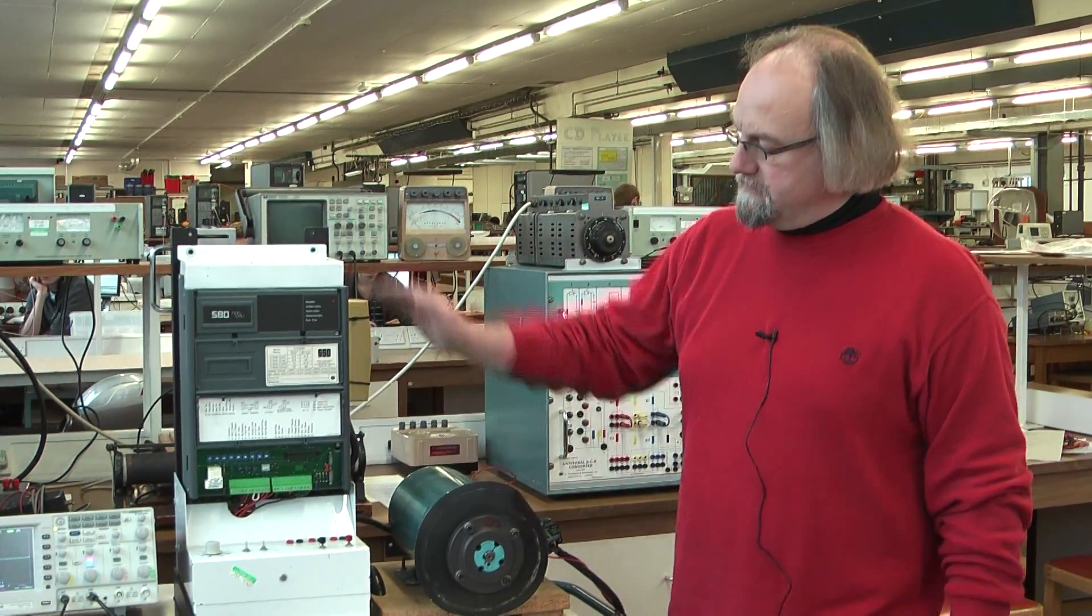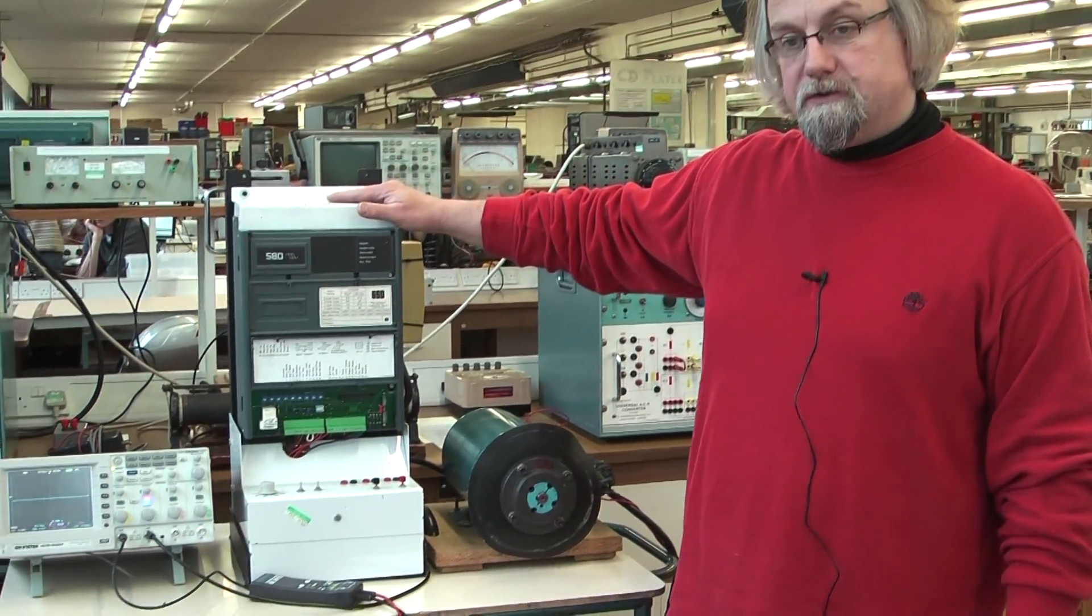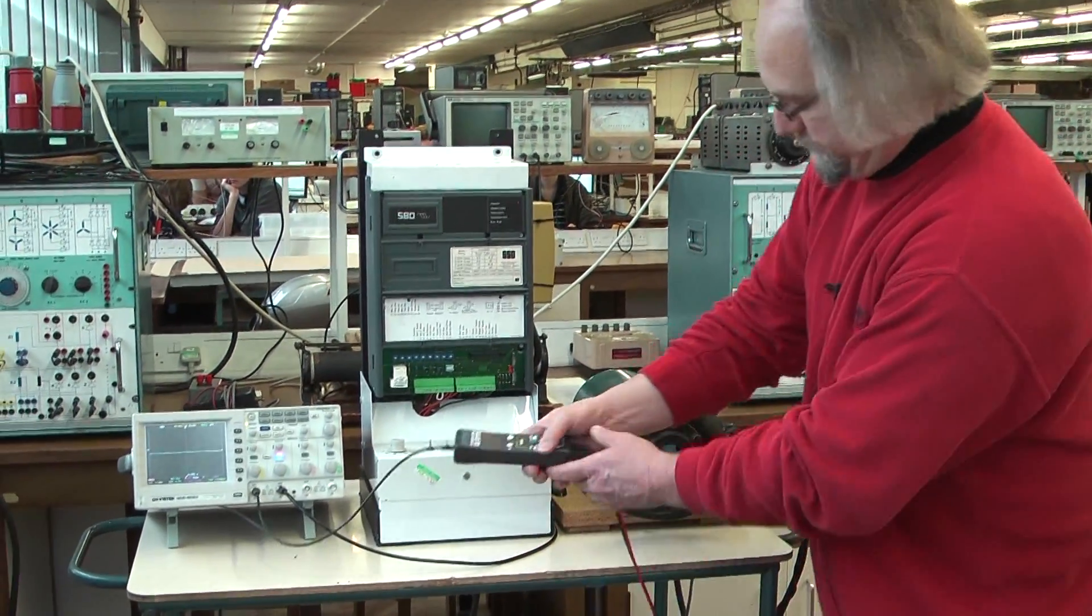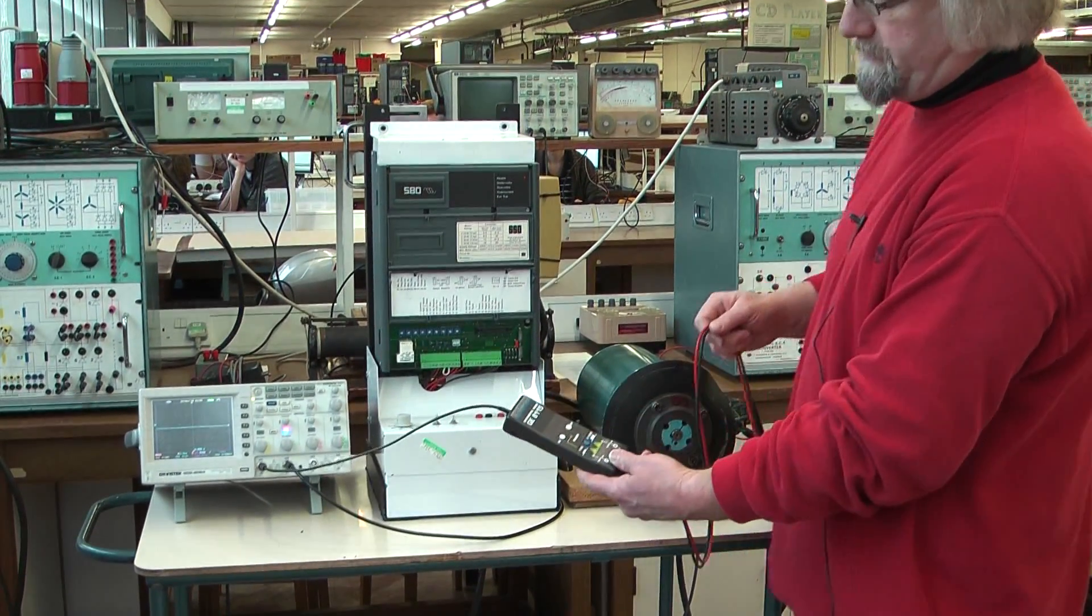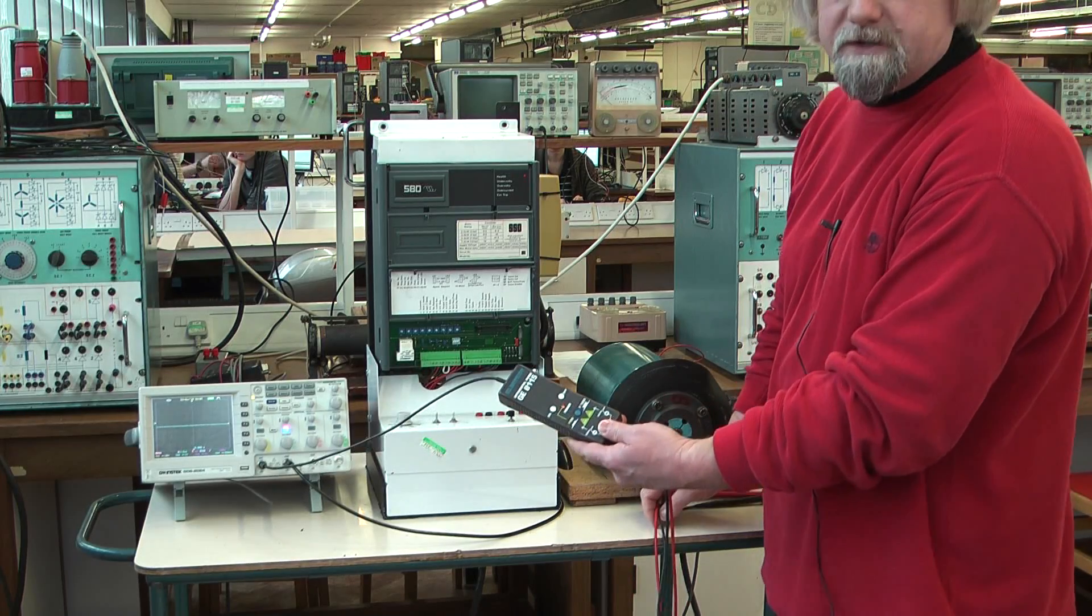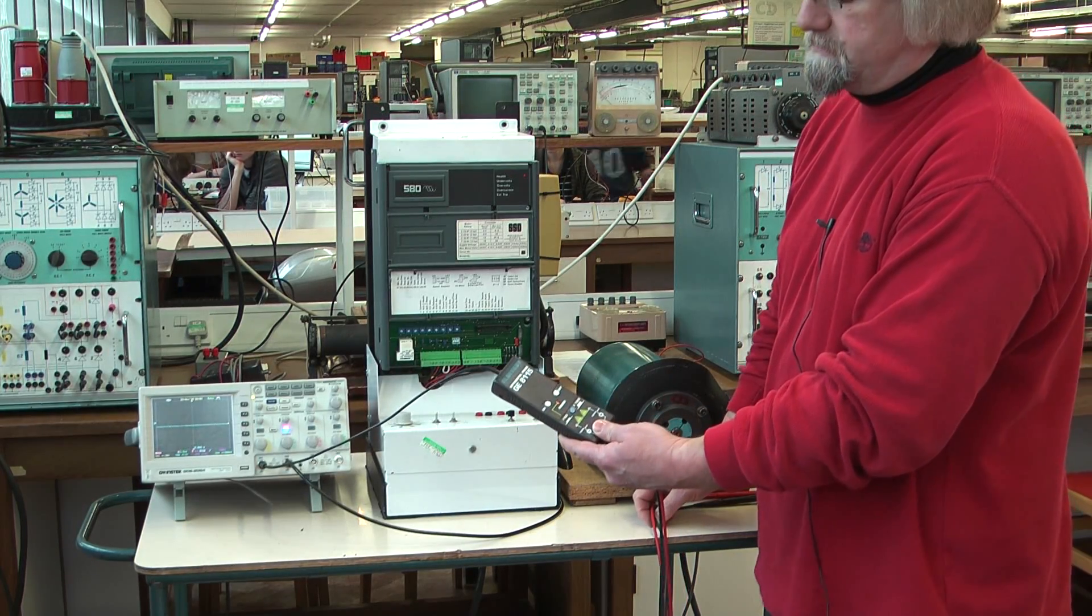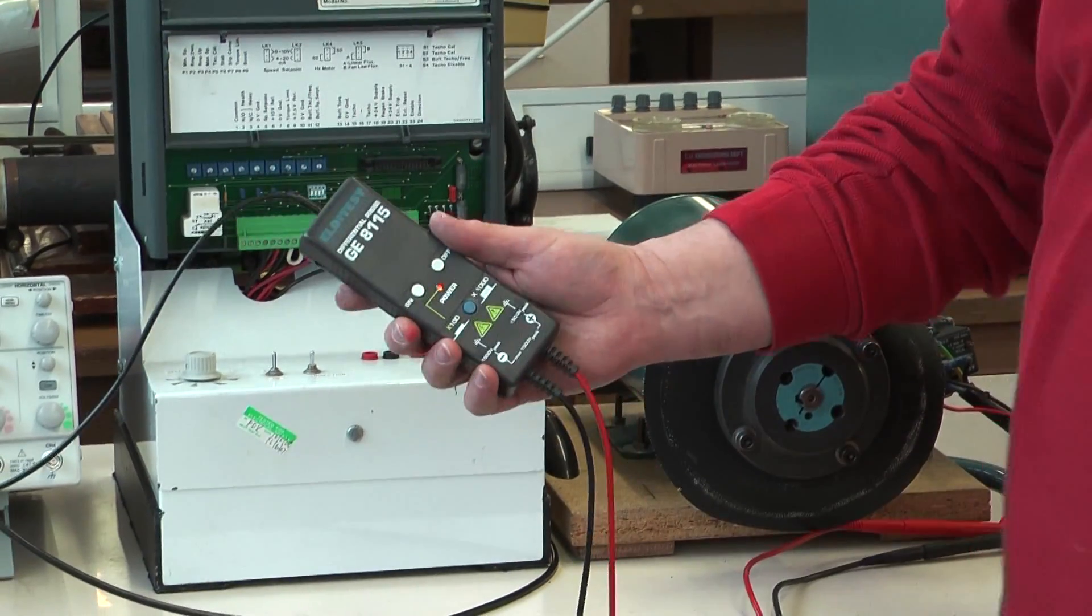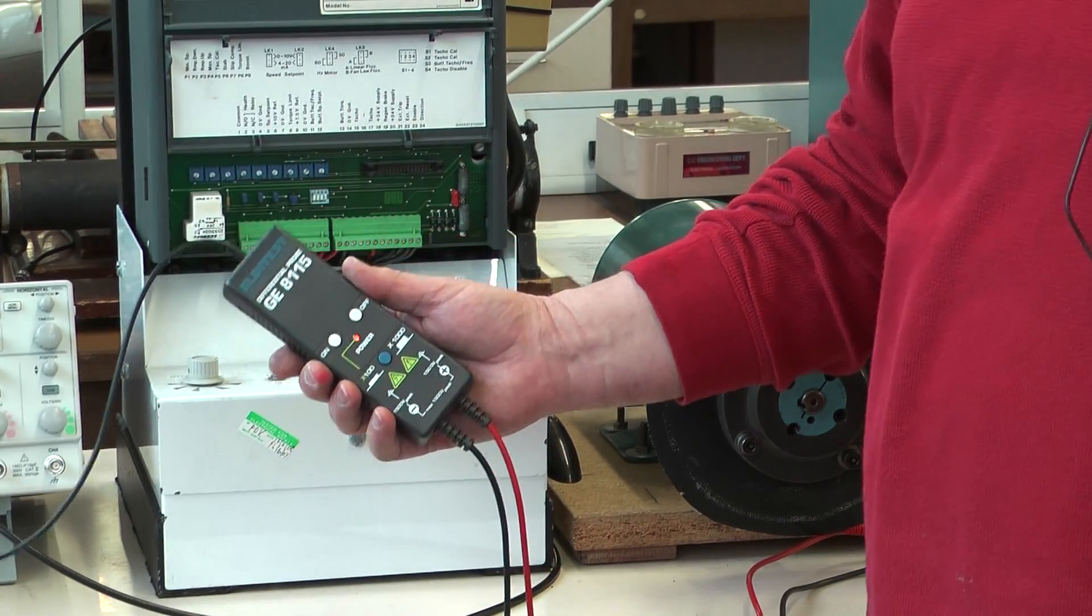Here's an induction motor. Here's the induction motor drive, often called an inverter. We're going to measure the voltage on the motor across two windings using the differential probe. This keeps us safe and isolates the voltage. Don't do these measurements unless you have something like this to measure voltages.